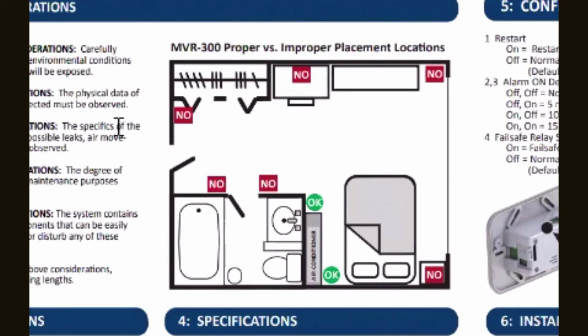Typical layout in some sort of occupied space, and this is what I'm highlighting here. This diagram is a typical hotel room, which is a big application, but rehab facility, hospital, whatever, the details are the same. And what we're doing here is we're choosing locations where the appropriate places for an MVR-300. And really, it's right around that VRF system that's inside the room. The refrigerants that you use in VRF systems are heavier than air. They're going to migrate to the floor, and they're going to concentrate on the floor. We talked about this earlier in the call before we got going officially.